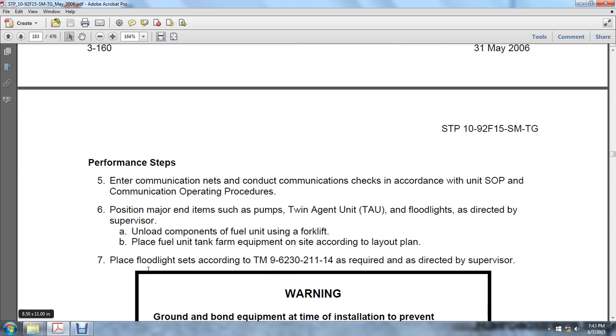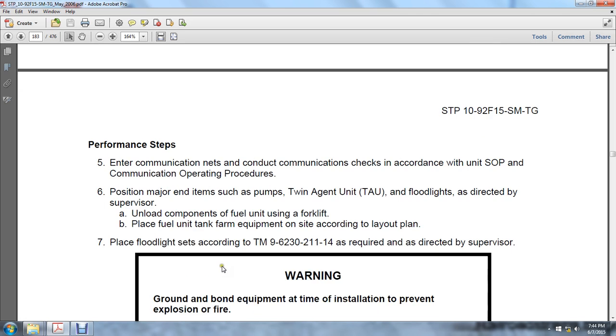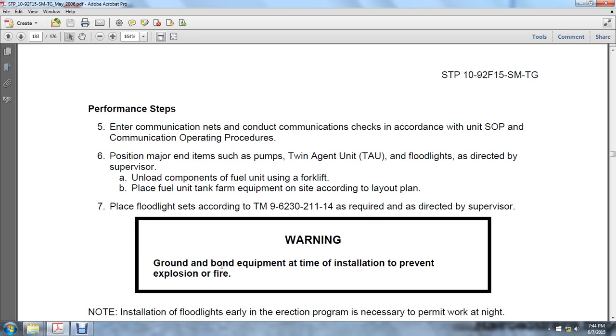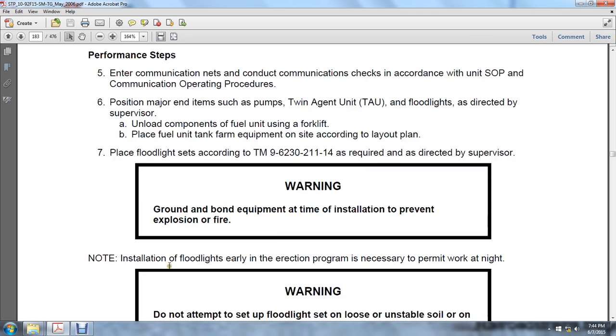Position major items and major end items such as pumps or twin agent units and floodlights as directed by the supervisor. Unload components with a fuel unit using a forklift. Place the fuel unit and tank farm equipment on the site according to the layout plan. Place the fuel set according to TM 9-6230-211-14 as directed by the supervisor. Warning: ground and bond equipment at the time of installation to prevent explosion or fire.